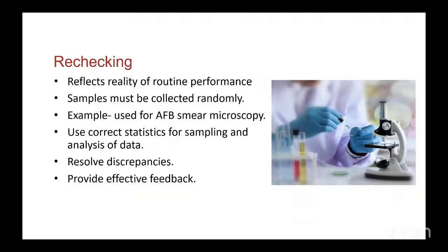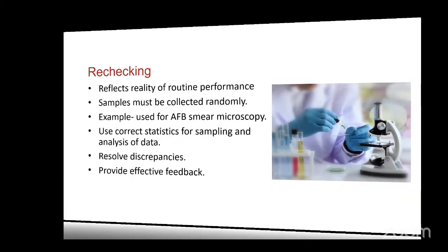Now, rechecking reflects the reality of the routine performance. Samples must be collected randomly for the rechecking process, for example in AFB smear microscopy. Use correct statistics for sampling and analyzing the data. Then you have to resolve the discrepancies, then provide effective feedback when the rechecking is done.